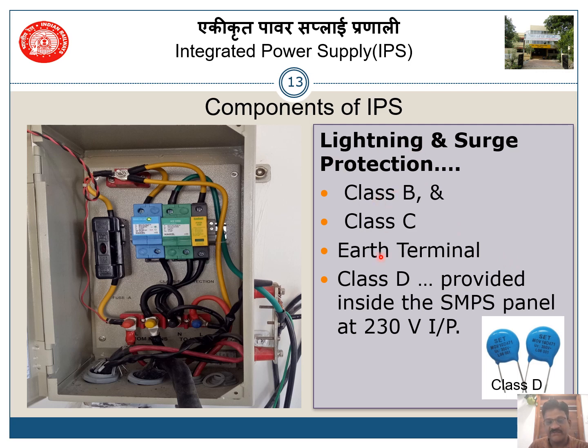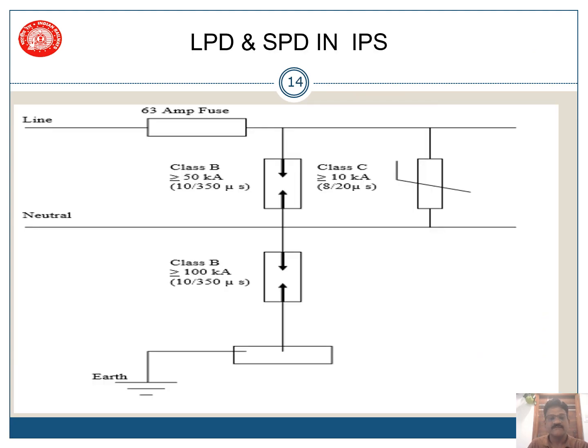In IPS, if you see, we are using class B and class C. So this is an IPS: class B, class C, earth terminal, and class D is also provided inside the SMPS panel. Generally, these are MOVs provided. But nowadays, we are providing class C only. This is an example of how LPD and SPDs are connected in IPS.